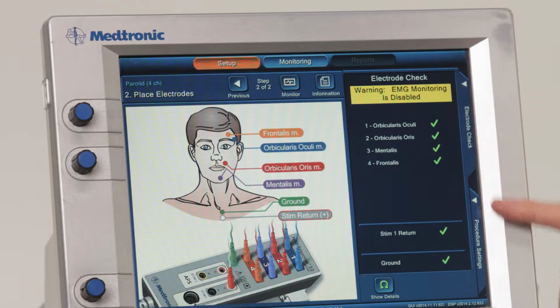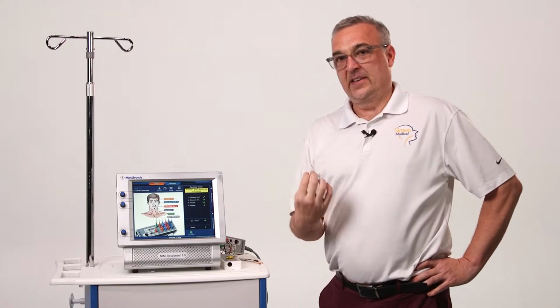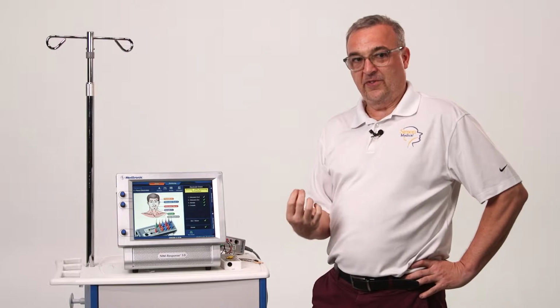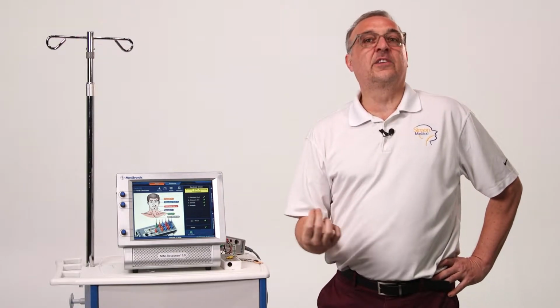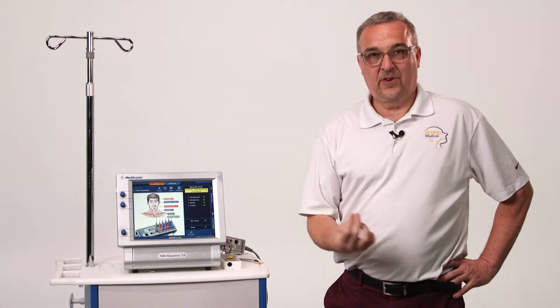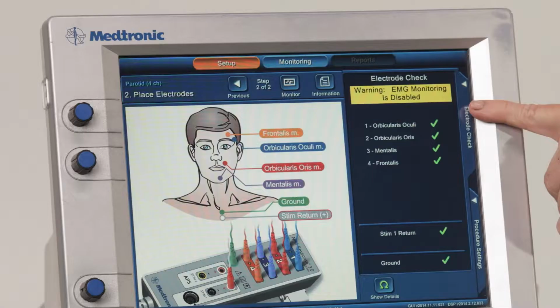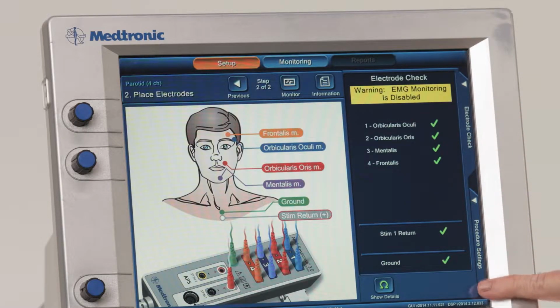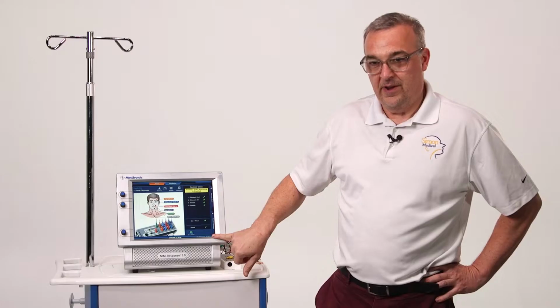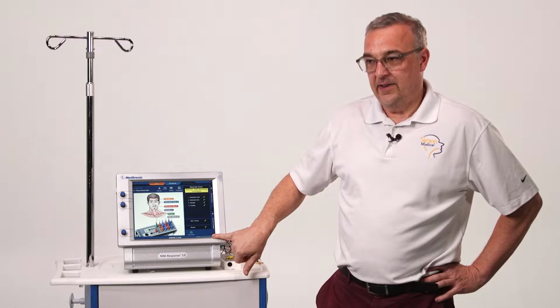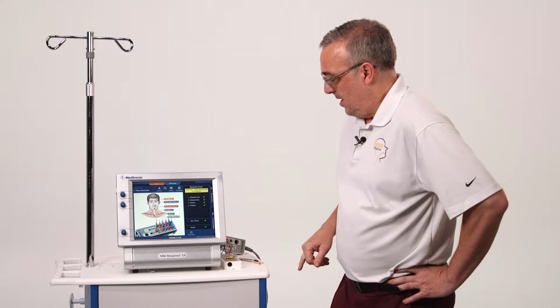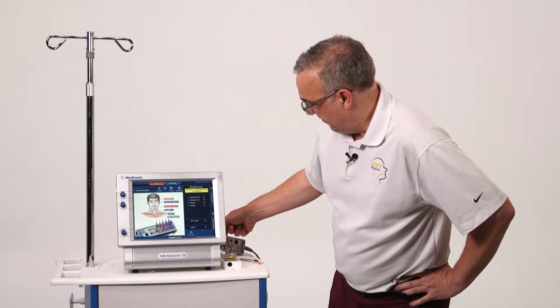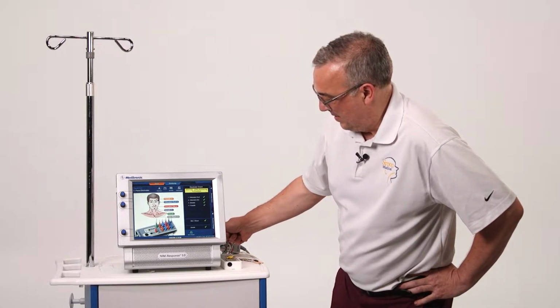Okay, we're already connected, so there's an electrode check, and what that does is it monitors the impedance of our connection. So we want to make sure we've got a good circuit or a good connection with those electrodes and the machine. Now, right now, it's green. So it's very simple on the new model. It just gives you a yes or no. The old ones were a number, and you had to know it was below 1. I'll show you what happens if we don't, because I want you to be aware of that.